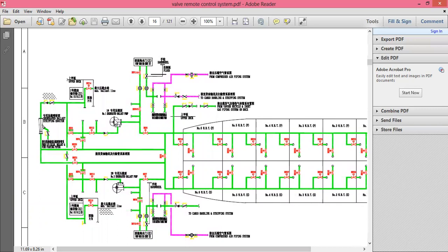So what you do, the suction side of the pump should be open first. So this CHS you close, this you close, open this valve, open the tank valve. So water from the tank is going to come into this pipe and it is going into the suction of the ballast pump. Now open the overboard valve, open this discharge valve. These two valves you open. Only the main discharge valve should be kept closed when you're running the pump. Water is already there on the suction side. Start the pump. Once the pump is started, open the discharge valve.